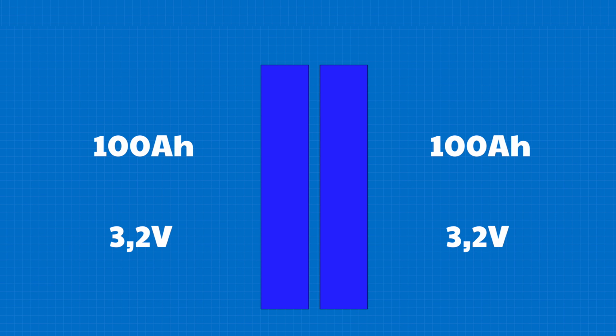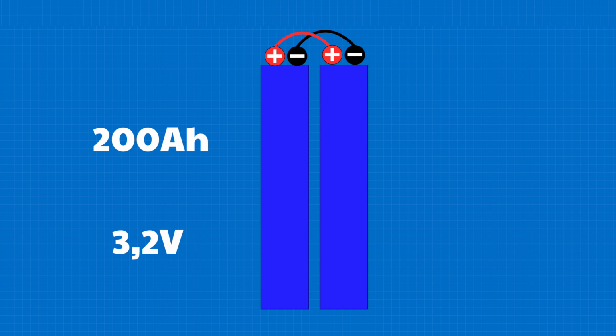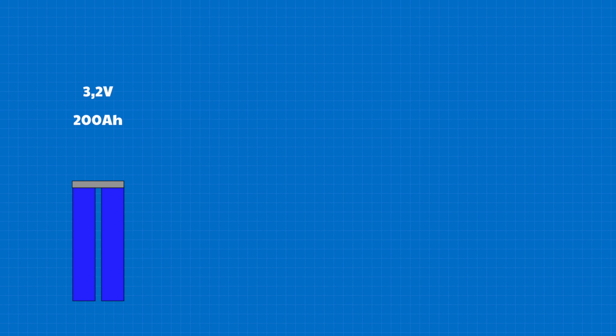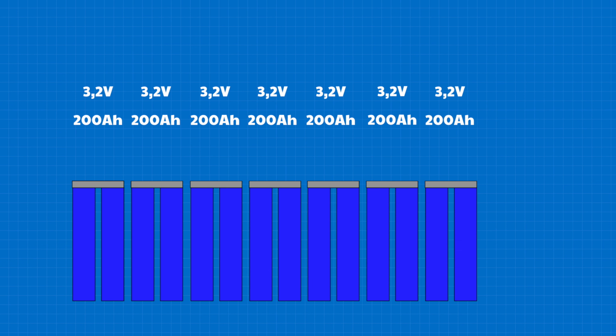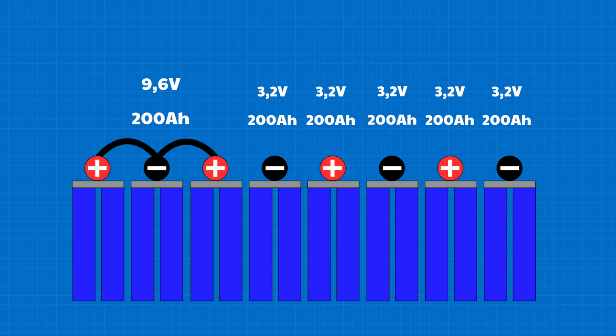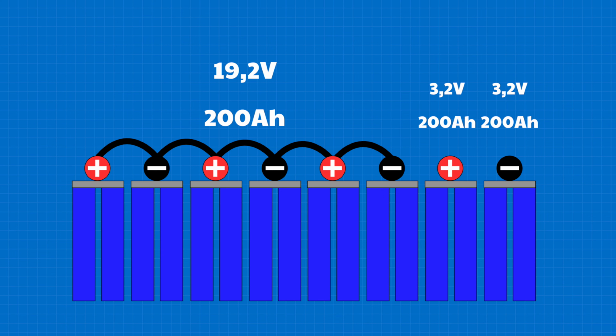8 sets of 2 are put in parallel, which doubles the capacity to 200 amp-hour. Then those 8 sets are put in series, which multiplies the voltage by 8. So 3.2 times 8 is 25.6.